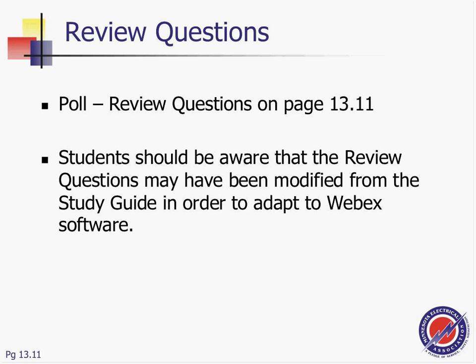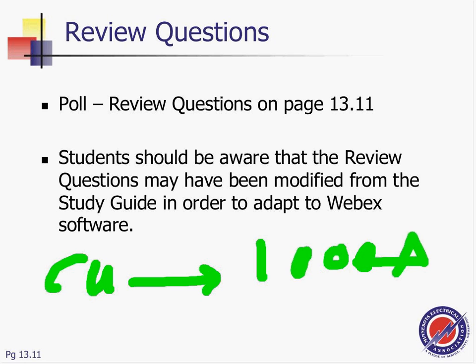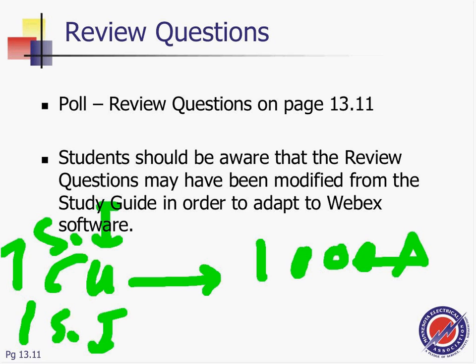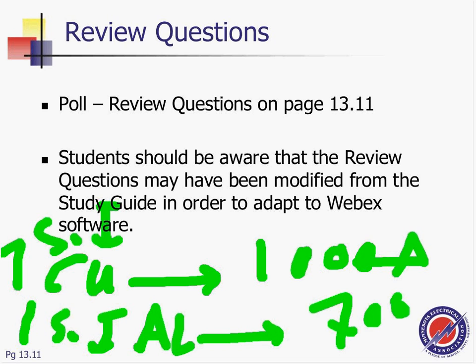I'm going to bring to your attention, guys, the copper bar. Remember, copper can carry 1,000 amps for each 1 square inch. If it's 1 square inch of aluminum, it's 70% of it, which is 700. I know I talked about it last time. That was on my master exam when I took it.